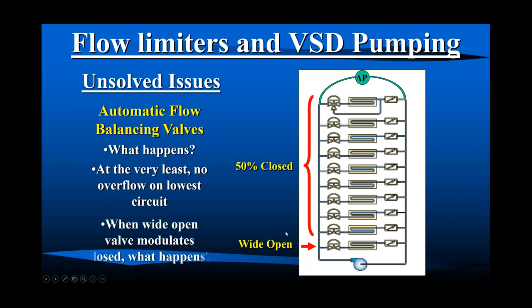So when this valve starts to modulate closed, that pressure goes here, and there's a certain increase in flow. If it's below the flow limiter cut-off GPM, the flow limit, say it's 10 and this is 8 and then it goes to 9, the output of this coil changes until this valve modulates back down. And then it occurs here, and then it occurs here until it gets to our pressure transducer, and then this modulates the speed of our pump down.